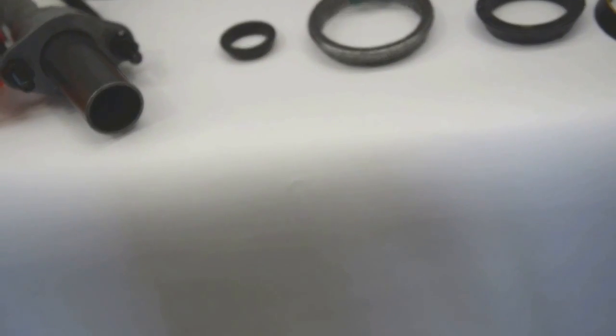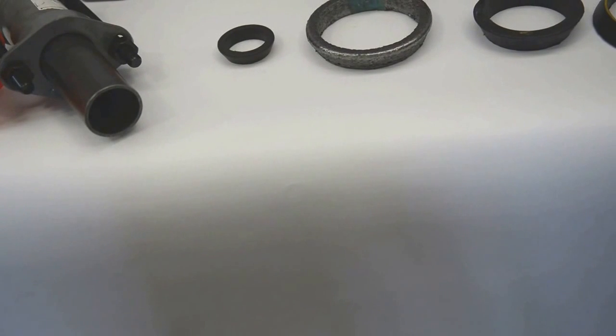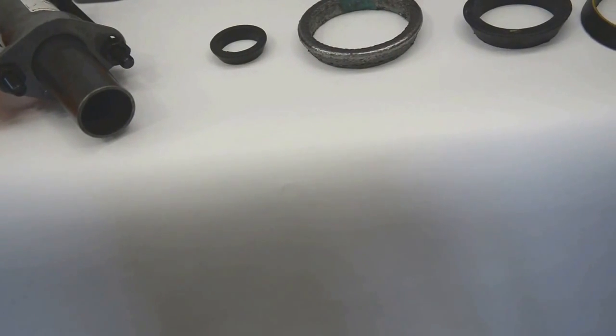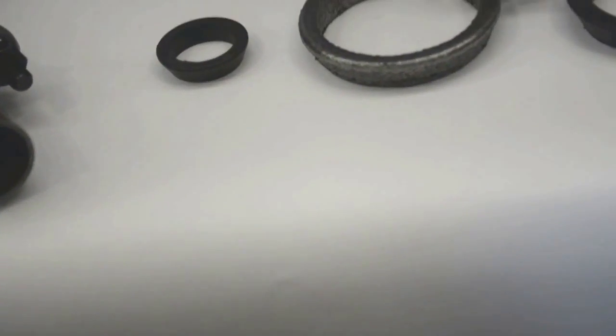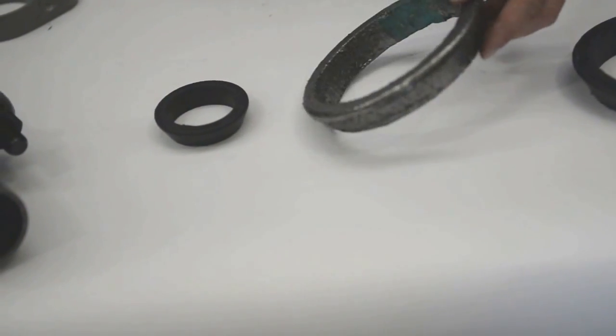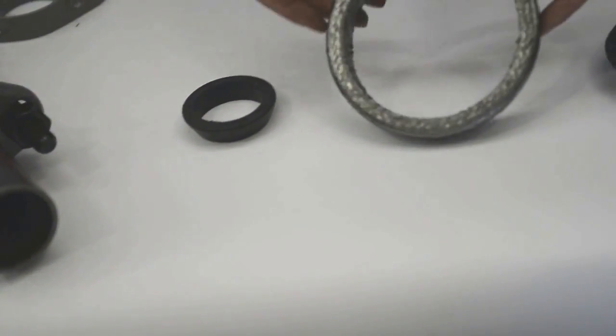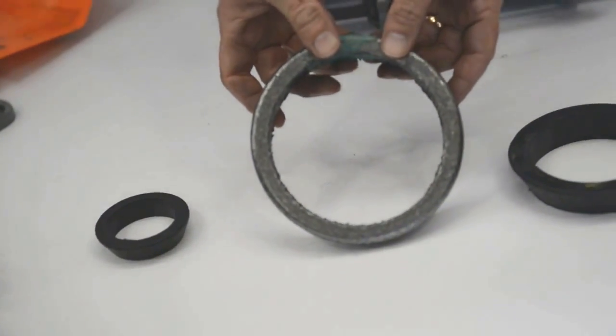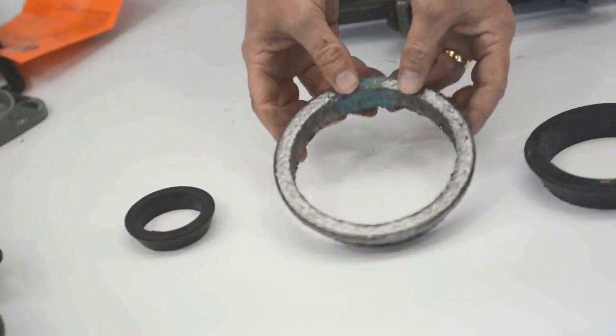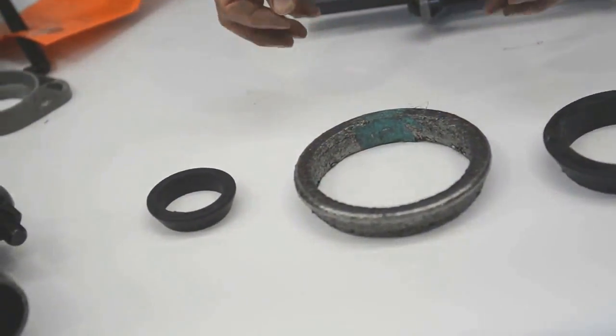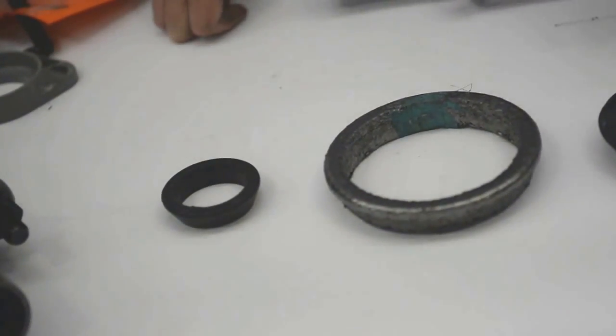This silver one, this is their high temp gasket. It's for low pressure steam applications as a general rule. It is a braided graphite impregnated cloth, so it is spliced together because it's not a molded gasket. It can go up to 1200 degrees Fahrenheit. It is a low pressure gasket.